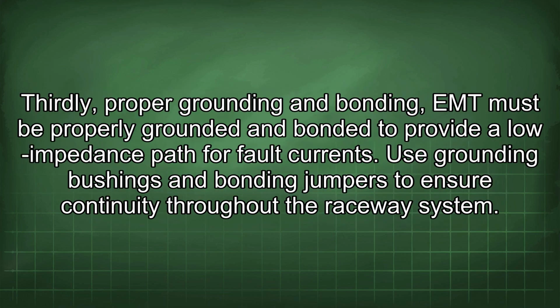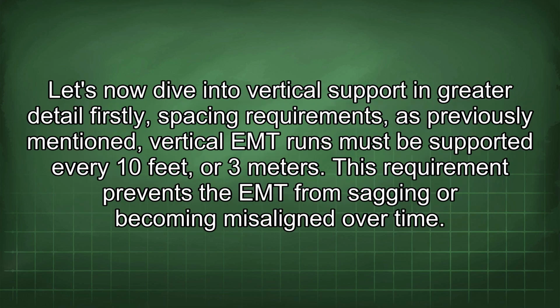Thirdly, proper grounding and bonding. EMT must be properly grounded and bonded to provide a low impedance path for fault currents. Use grounding bushings and bonding jumpers to ensure continuity throughout the raceway system. Let's now dive into vertical support in greater detail.